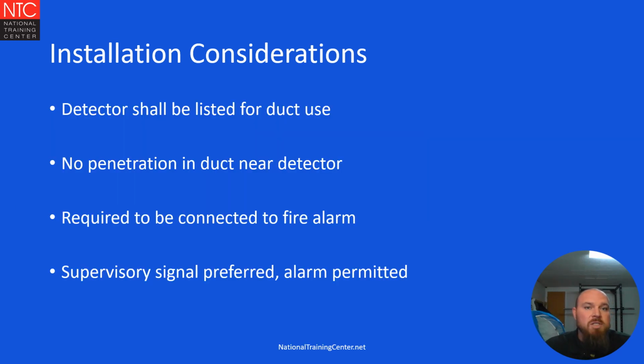Some installation considerations when we have duct detectors. The detector itself has to be listed for duct use. You can't just put a regular smoke detector head in there. It does have to be a specifically listed duct detector. You're not supposed to have any penetrations in the duct near the detector, as it will start to mess with the detector's ability to sense smoke coming in.